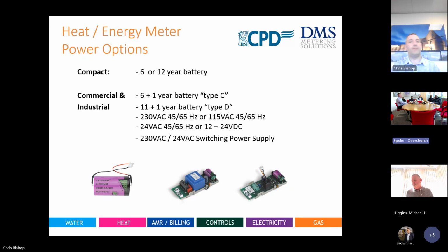Generally, commercial and industrial, you have way more options. Mains, 24-volt, switching power, AC, DC operation, that sort of stuff. That's more relevant for the commercial and industrial, and that's a standard because there's more data required for that, because that's an energy profile, it's control, it's asset management as well, it's alerts, alarms. You need data very quick. And like I say, with mains power, you've constantly got that power there to provide data every 15 seconds with no issue in the background at all.